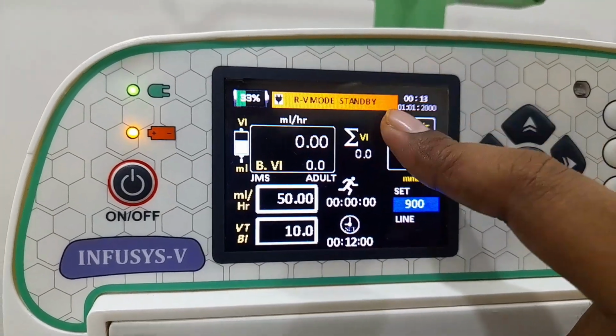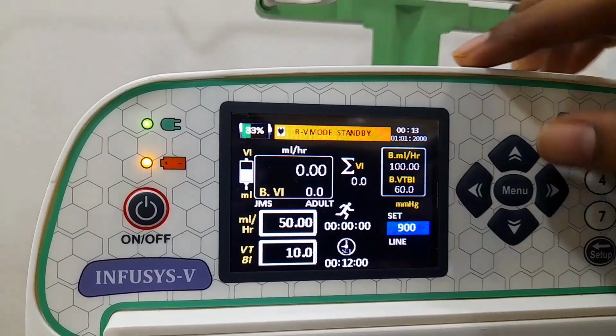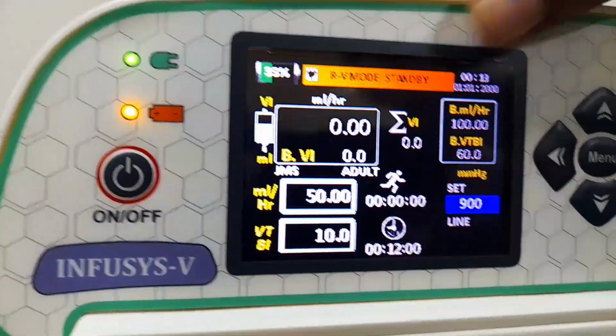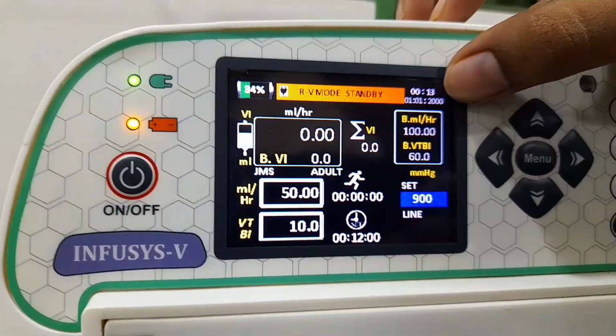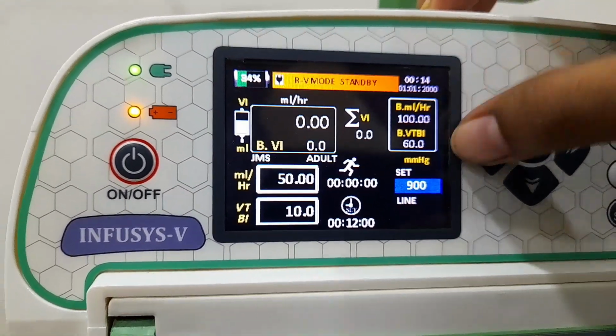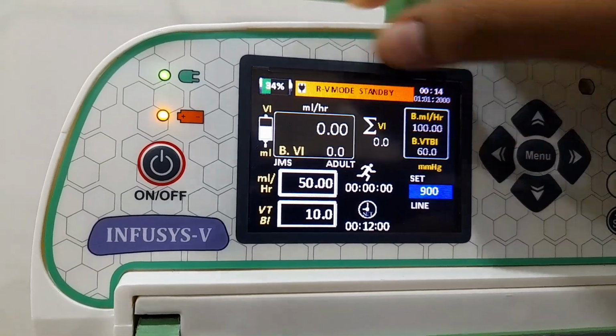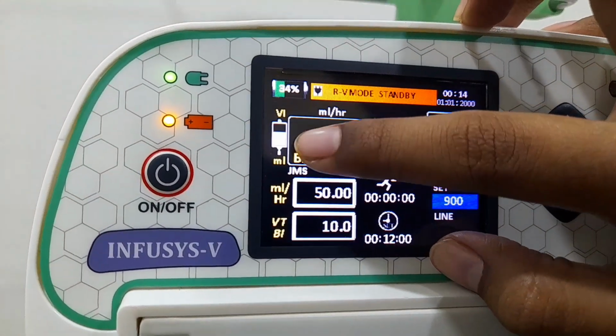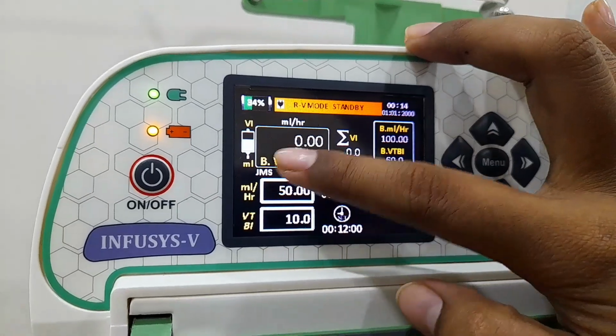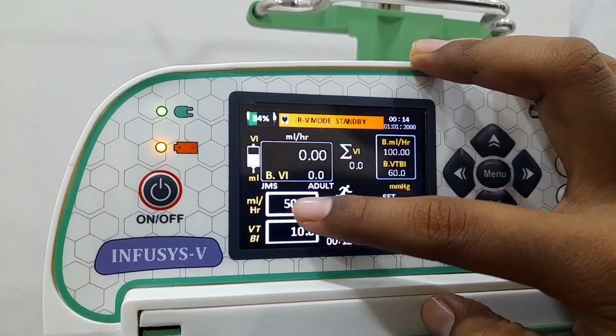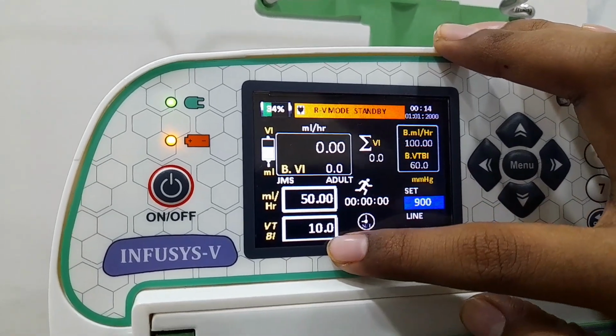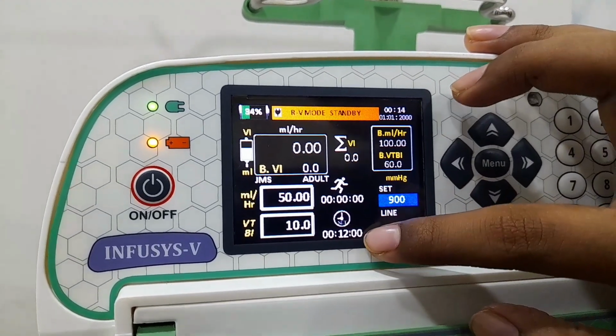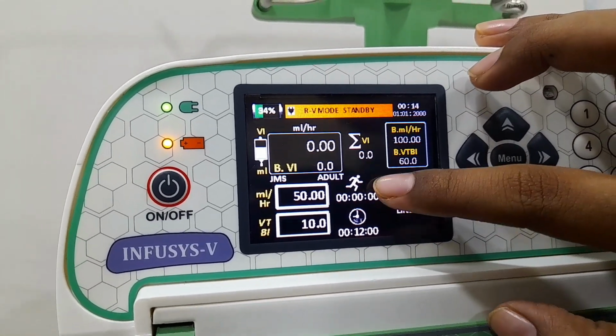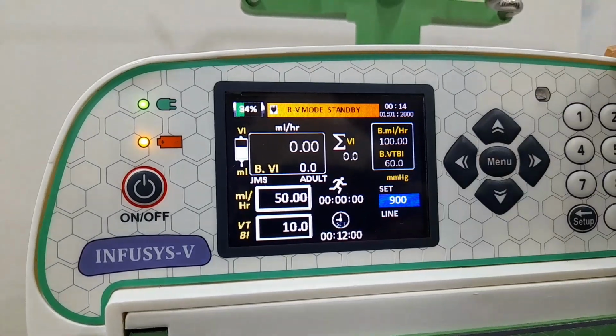Now we can see the home screen parameters. This is the status bar where we can see the current status of the pump like running, bolus condition, pulse condition, and this one is the battery backup percentage. You can also see the real time and date, month, and year here, and bolus parameters like bolus volume and bolus rate, and a progress bar for infusion status. Based on this bolus rate and volume, the bolus volume infused will appear here. And then the IV set and IV set brand as mentioned before. You can see the set rate and set volume because this is in the RV mode. Based on the set rate and set volume, we can see the calculated time here and elapsed time. Also the occlusion set and inline graph.